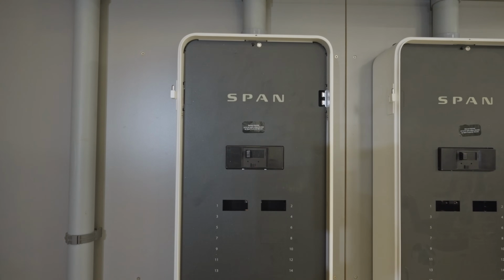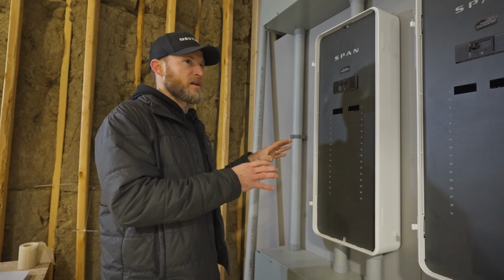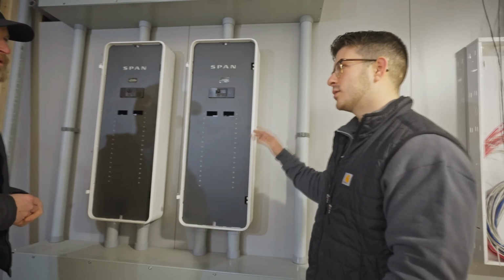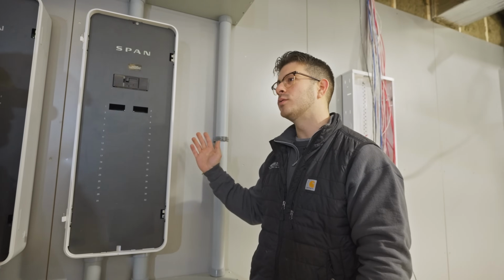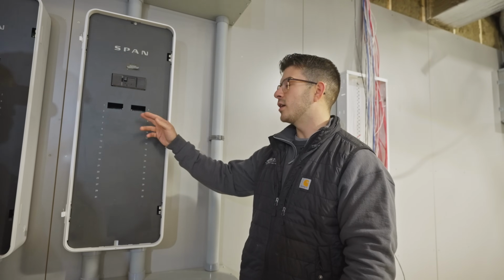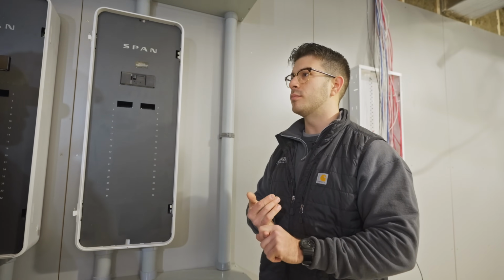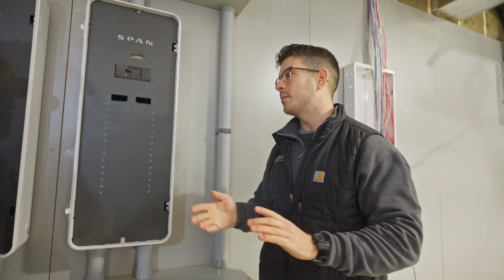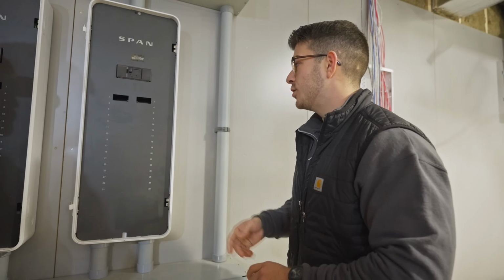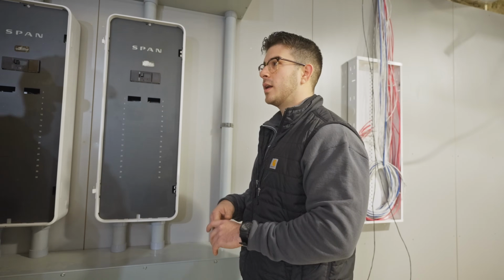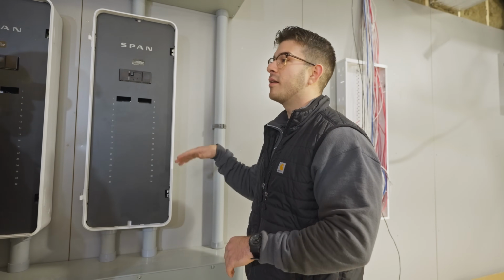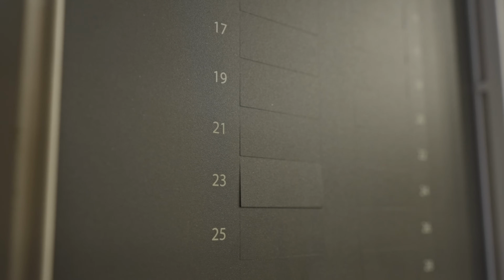The benefit of using Span is that it still just uses regular breakers. You can dumb these panels down to work as a conventional load center. There's regular breakers in here, you can use any standard breaker pretty much, Eaton, Murray, Siemens, whatever you've got, and you can flip them individually as you want. If you were to lose Wi-Fi or the low voltage, everything will still work conventionally.